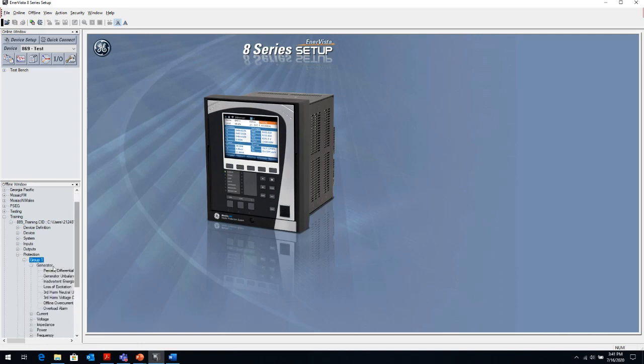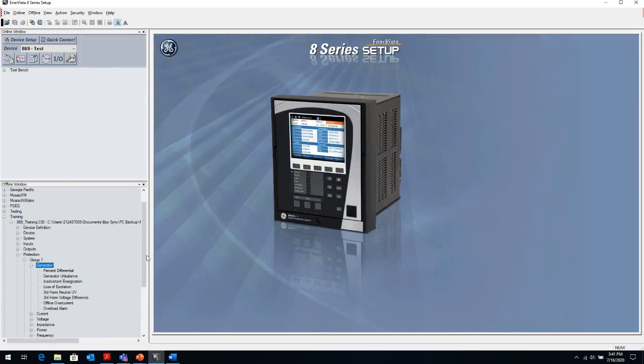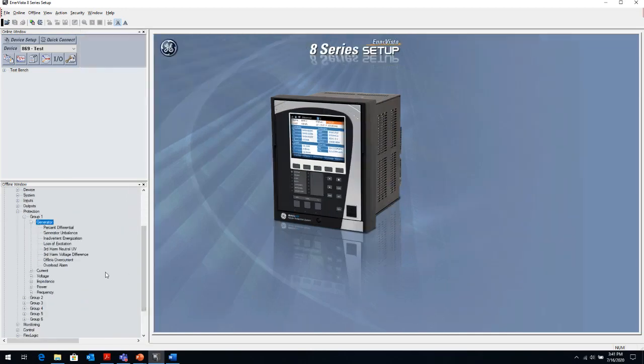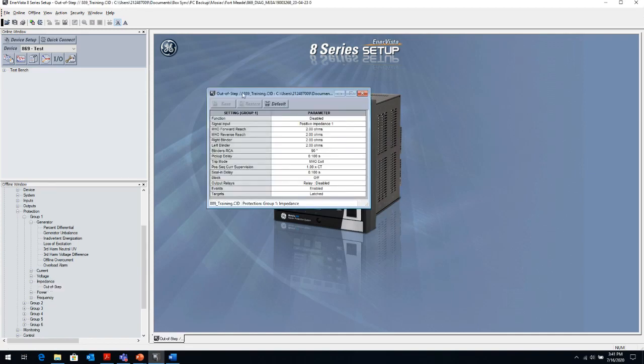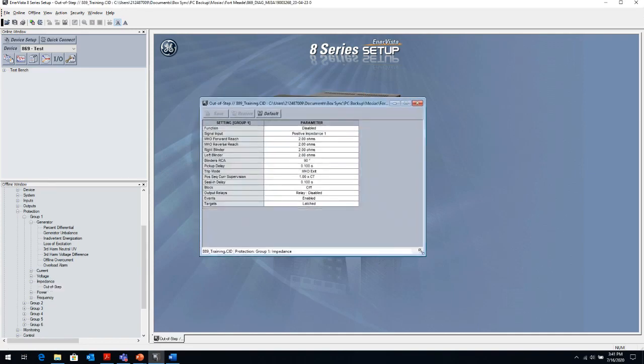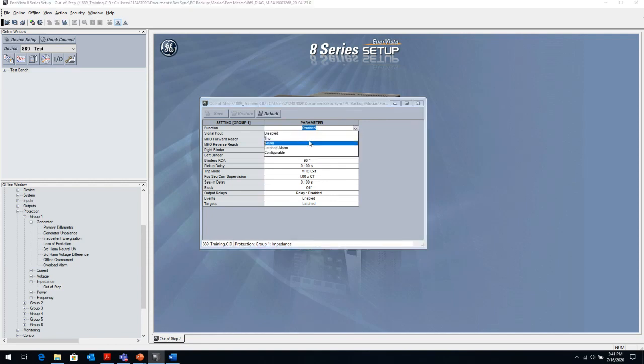The only element I mentioned that's not part of the quick setup screen was the out of step condition. And I just wanted to show you the out of step condition we talked about. Again, I need to enable it to trip. Well, if there's an element like the out of step condition, maybe I don't want it to trip. Maybe I want to enable it to either block something or only alarm for me to know that I have an out of step condition and I might want to look at something. So I don't necessarily have to trip.